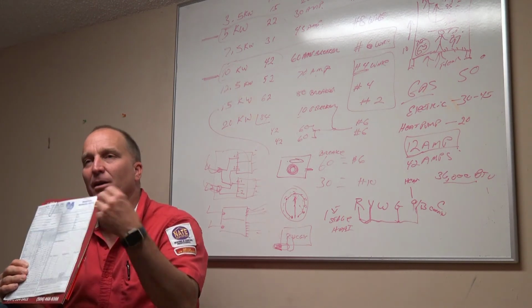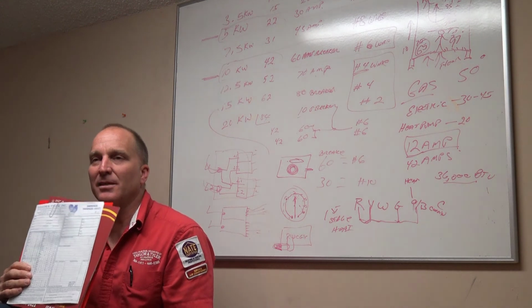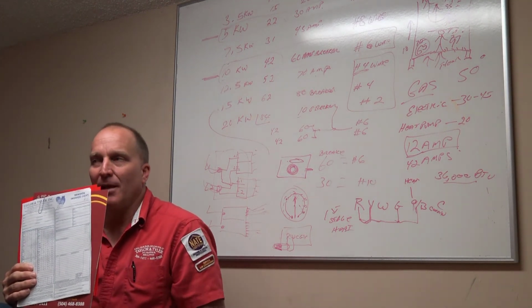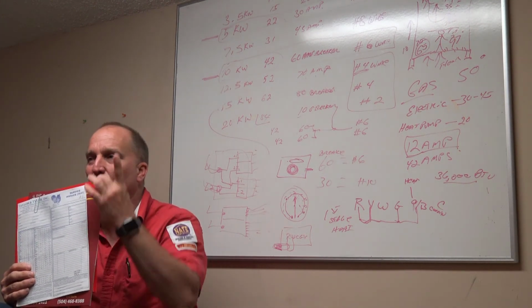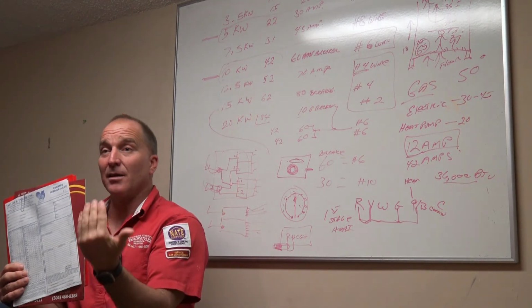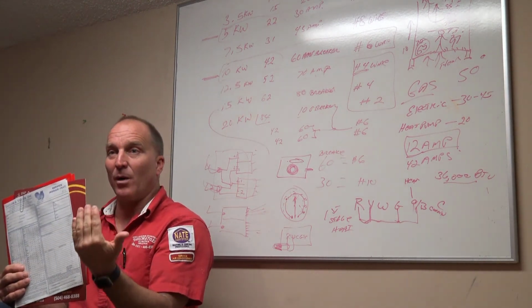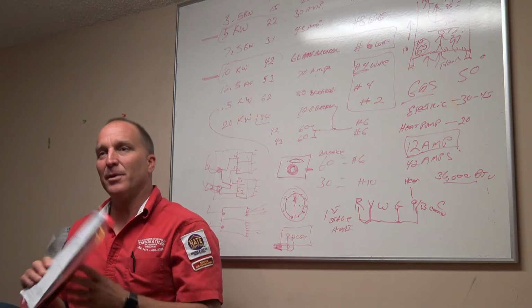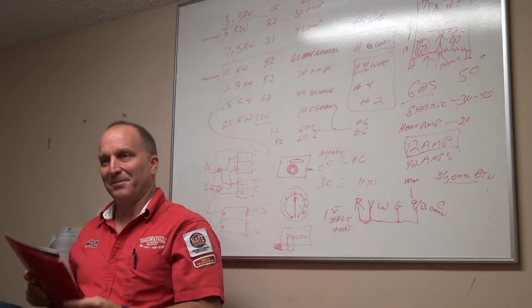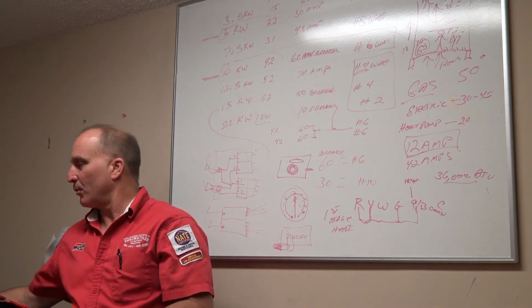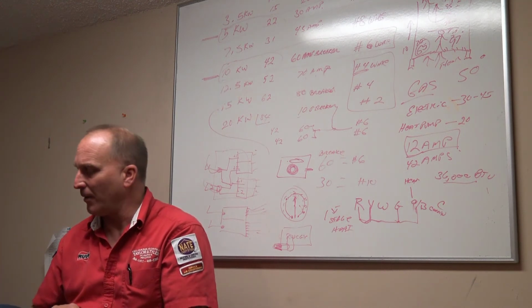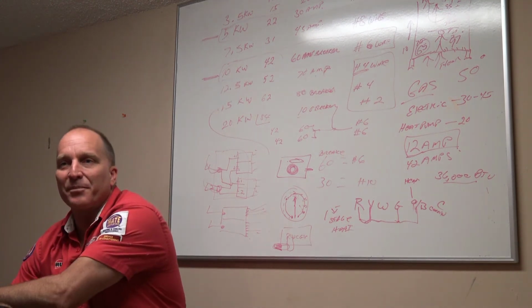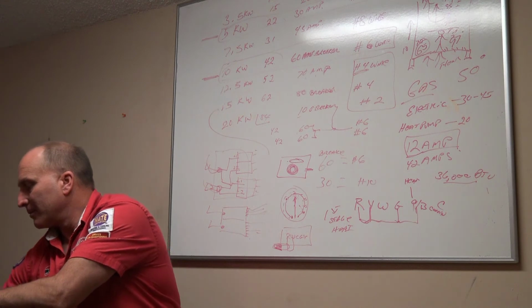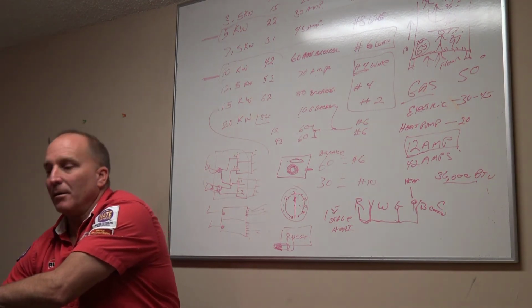Now, say I have nothing on there. Cousin Bill says it's just low on refrigerant. He goes and adds refrigerant to the system, drives his head pressure up, gets his suction pressure to where it's better than what it was, and they're cooling better. Cousin Bill was right. But he didn't do what was right. Prove it. It's cooling better now. You don't have any physical or visual proof. So they're going to take his word for it.